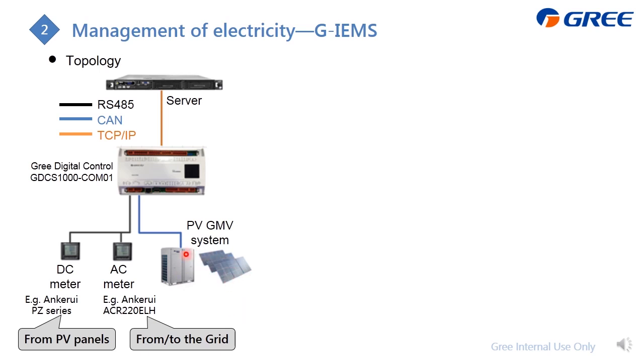For this system, from the master outdoor unit's G1, G2, you need to connect to this gateway, here is the model. You still need to install a power meter: one for DC, to measure how much power you get from the PV panels, and another for AC, to measure how much power you get from the grid power supply, and if available, how much power you can upload to the grid.